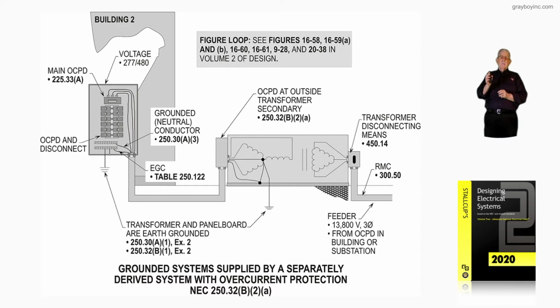It is fed from an upstream device. It could be in a substation or it could be in a building, as illustrated. But notice it's a high voltage. It's 13,800 volts, 3-phase. It's over 1,000 volts. And we say, yeah, it could be fed from a substation or whatever. Customer owned. So rigid metal conduit is housing those conductors. Burial depths in accordance with 300.50 or the designing engineer's recommendation. There's an overcurrent device outside at the transformer, so that makes that a feeder going inside the building.